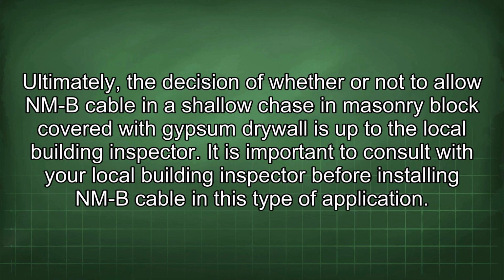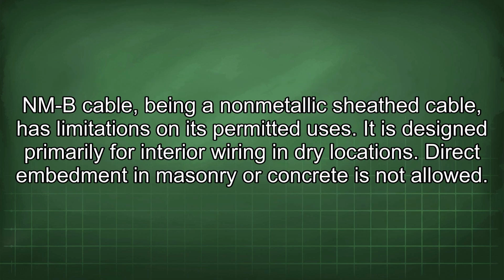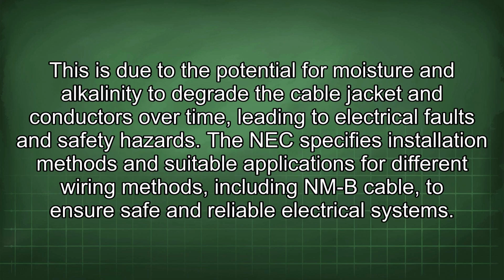Ultimately, the decision of whether or not to allow NMB cable in a shallow chase in masonry block covered with gypsum drywall is up to the local building inspector. It is important to consult with your local building inspector before installing NMB cable in this type of application. NMB cable, being a non-metallic sheathed cable, has limitations on its permitted uses. It is designed primarily for interior wiring in dry locations. Direct embedment in masonry or concrete is not allowed. This is due to the potential for moisture and alkalinity to degrade the cable jacket and conductors over time, leading to electrical faults and safety hazards.